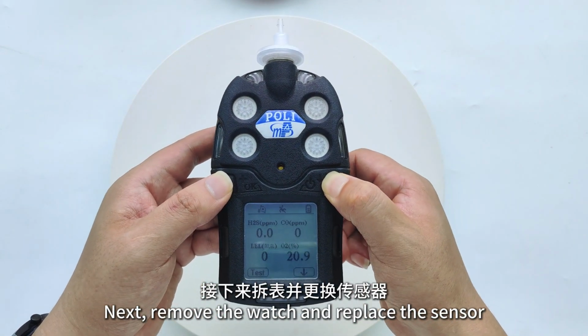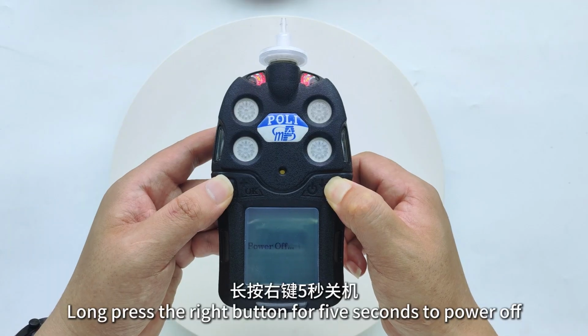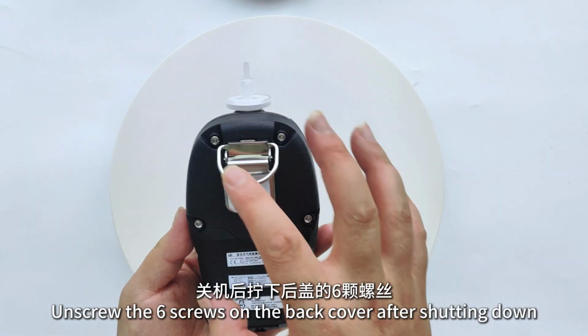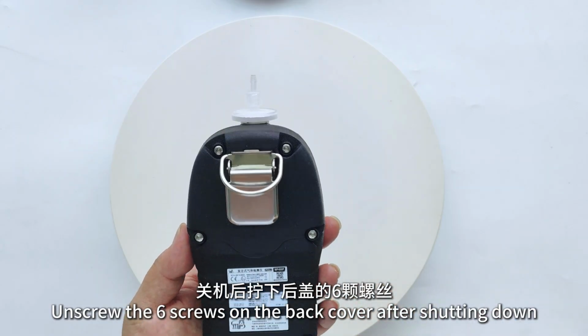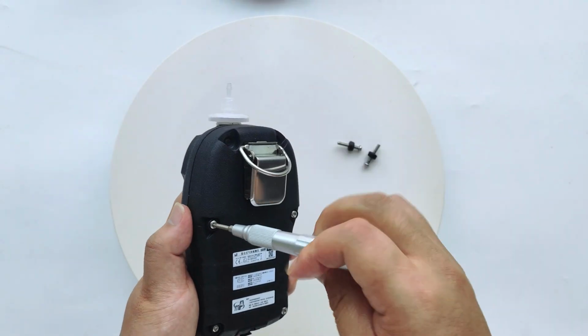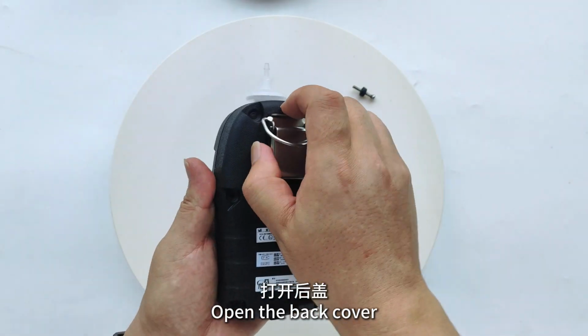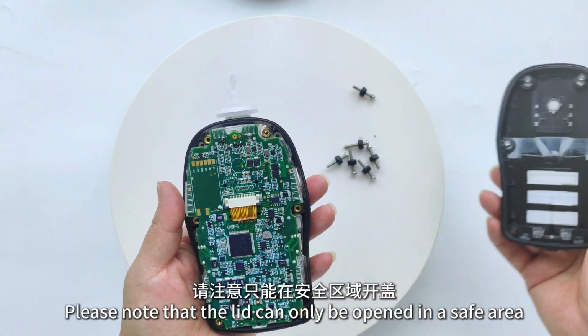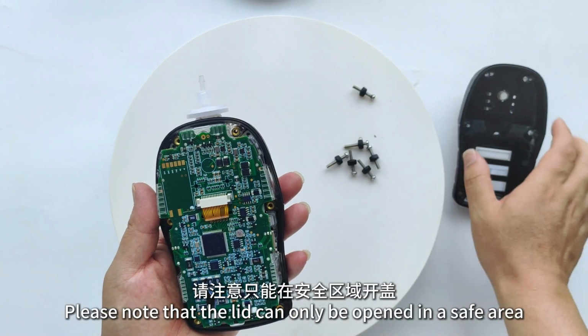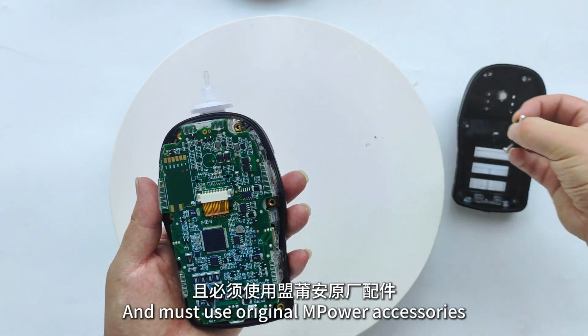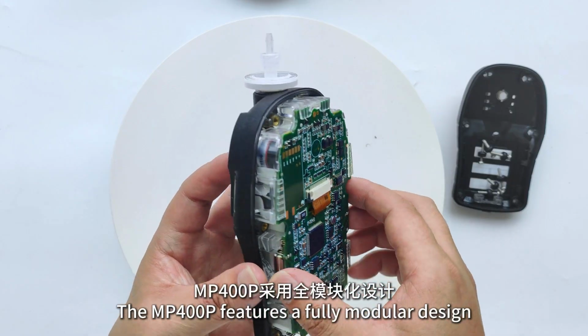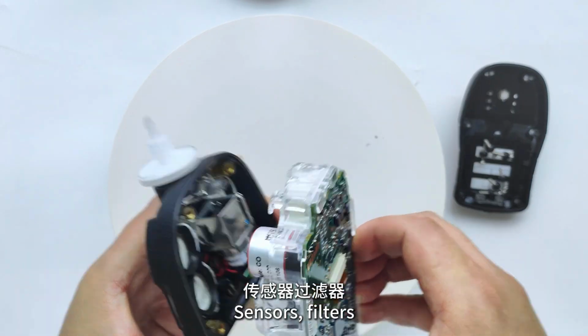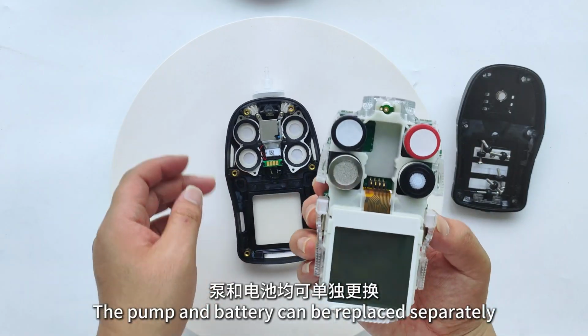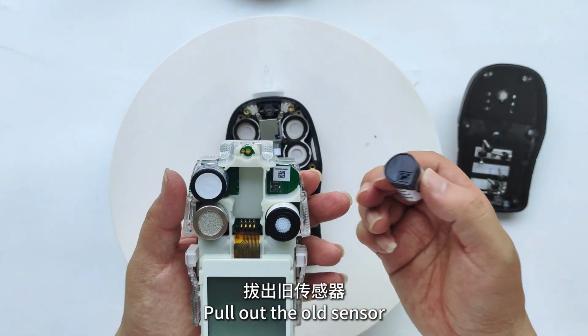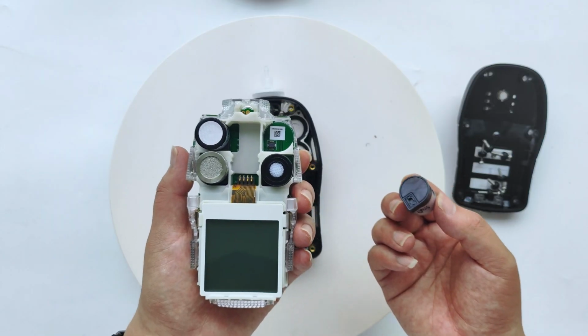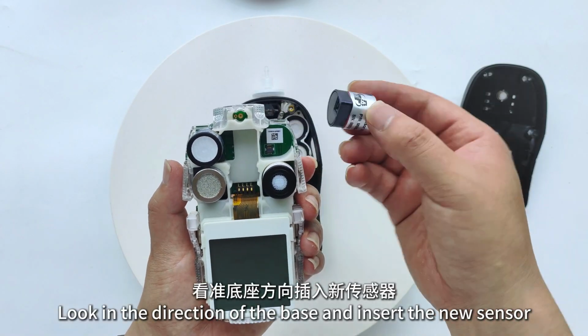Next, let's remove the watch and replace the sensor. Long press the right button for 5 seconds to power off. Unscrew the 6 screws on the back cover after shutting down. Open the back cover. Please note that the lid can only be opened in a safe area and you must use original mPower accessories. The MP400P features a fully modular design. Sensors, filters, the pump and battery can be replaced separately. Pull out the old sensor. Look in the direction of the base and insert the new sensor.